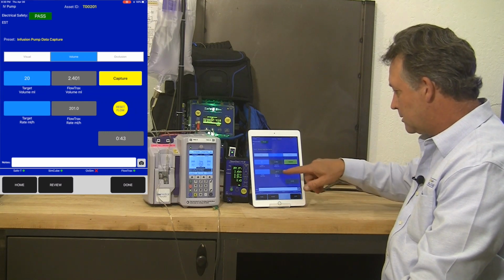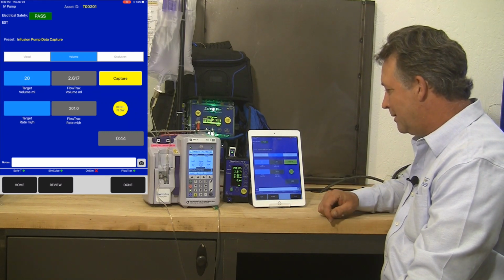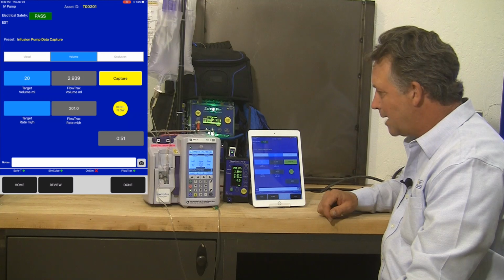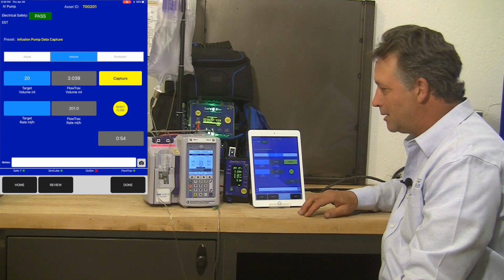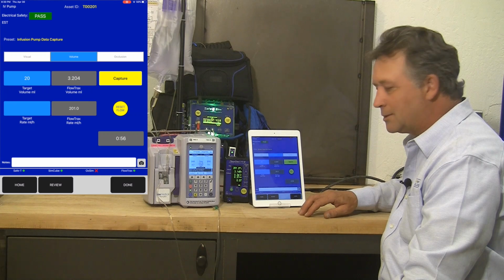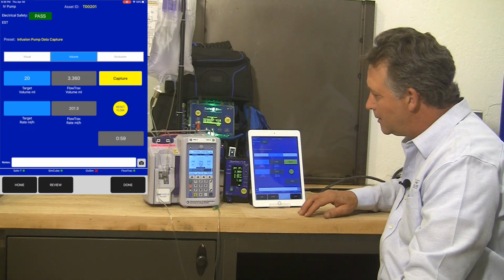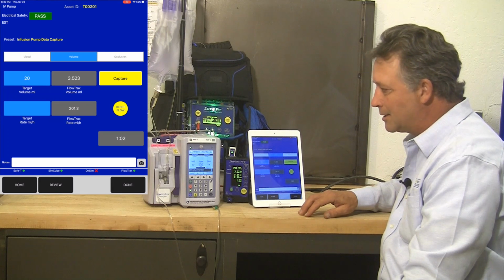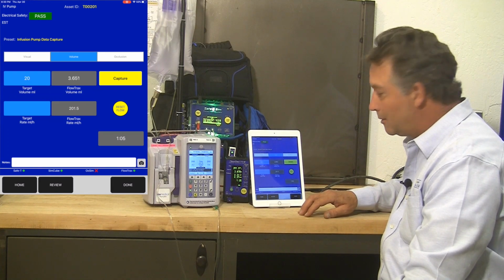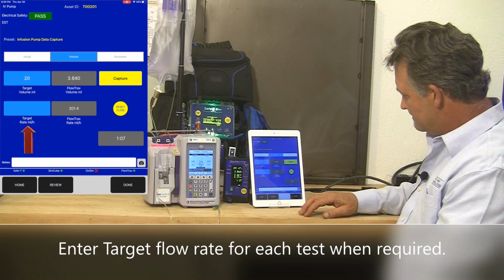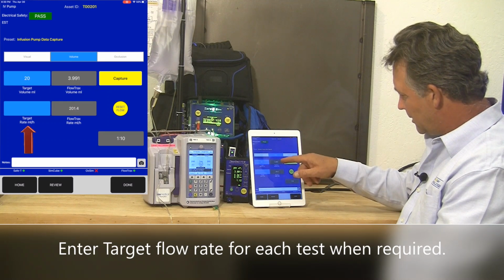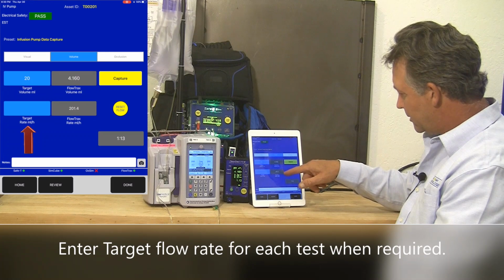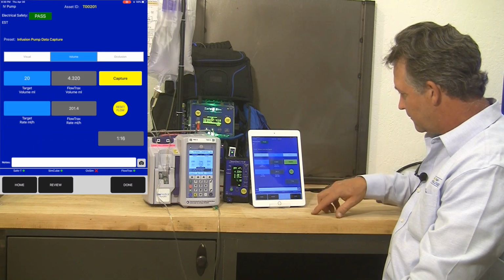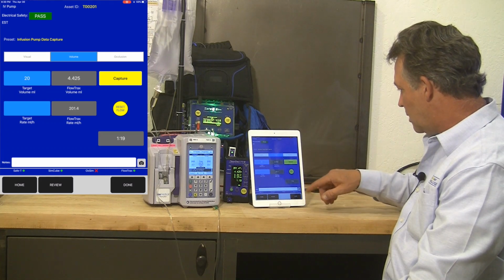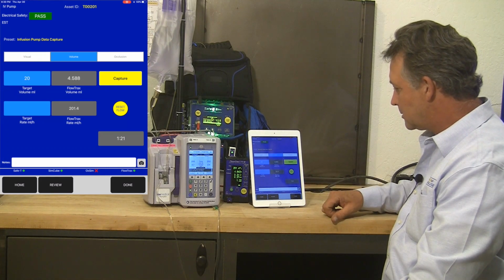We're 40 seconds into this and the rate is showing at 201.0 for the average flow rate. The FlowTrax is capable of doing 1% accuracy in 3 minutes or less, but oftentimes it's less than a minute with a good IV pump to be able to see what the long-term rate is going to be with the averaging algorithm that we use. So we've got the volume accumulated up to 4 milliliters. It's got to reach 20 before the pump stops. FlowTrax rate milliliters per hour is 201. Time elapsed is 1 minute 20 seconds.